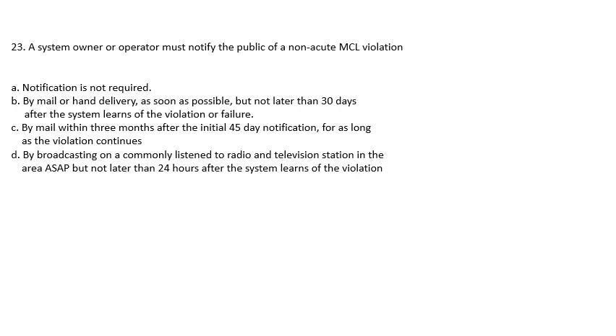Question 23: A system owner or operator must notify the public of a non-acute MCL violation within: notification is not required; by mail or hand delivery as soon as possible but not later than 30 days after the system learns of the violation; by mail within three months after the initial 45-day notification; or by broadcasting on a commonly listened-to radio and television station ASAP but not later than 24 hours. The answer is 30 days, as a Tier 2 violation.